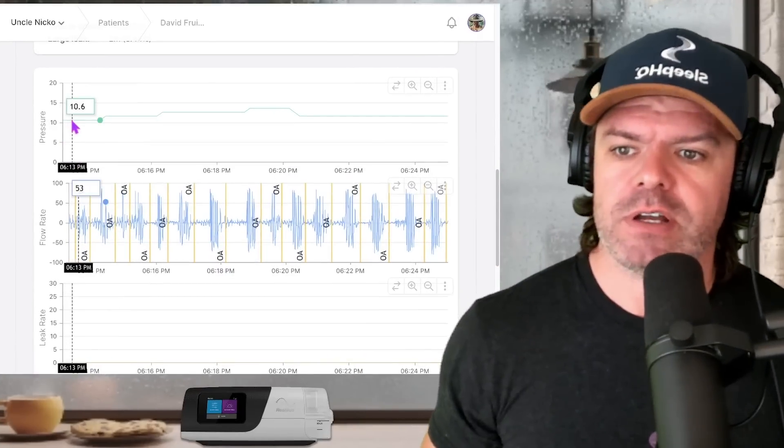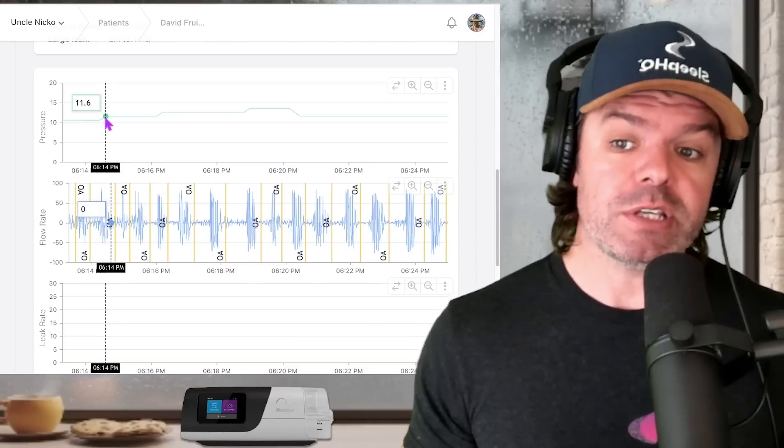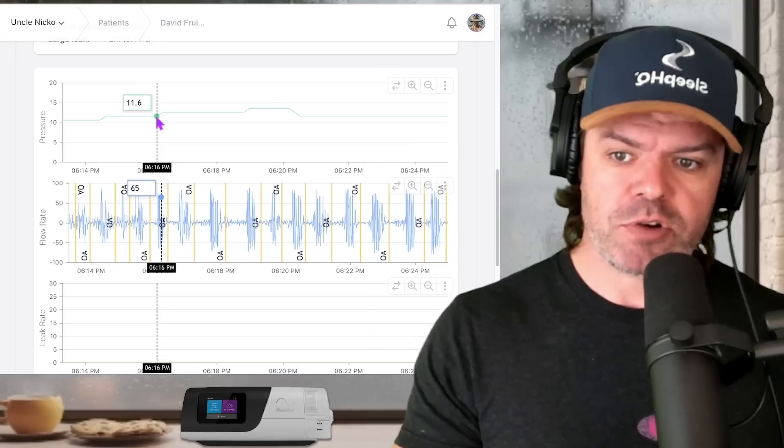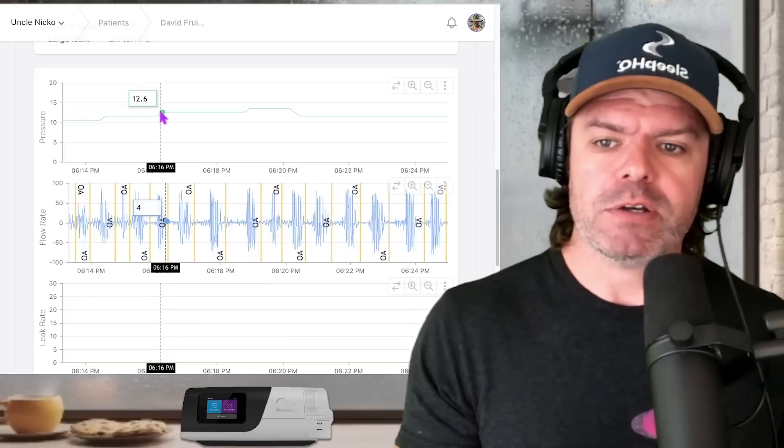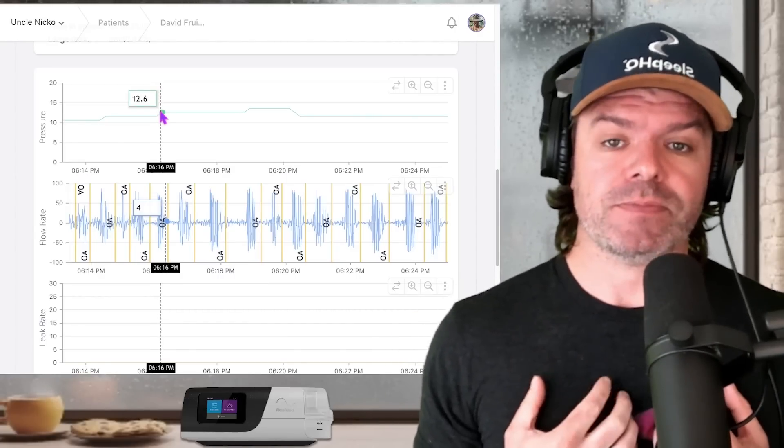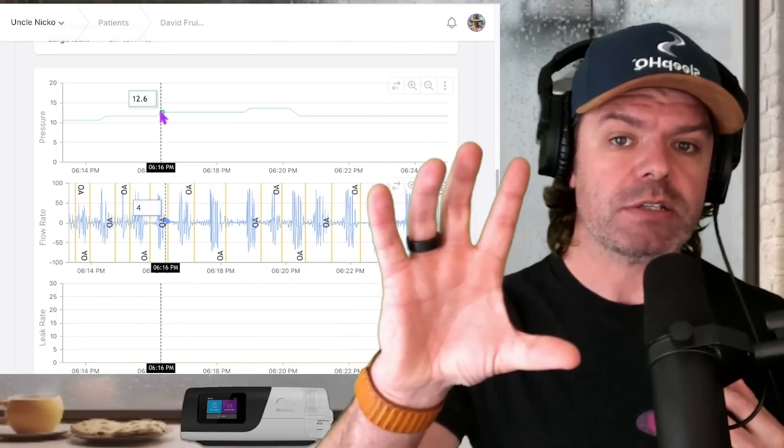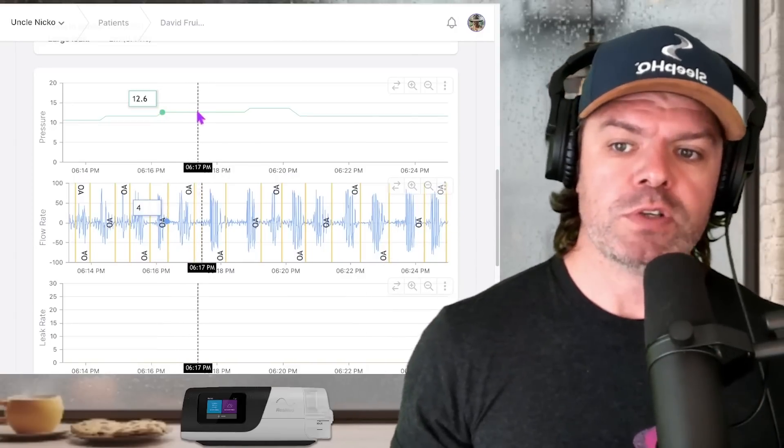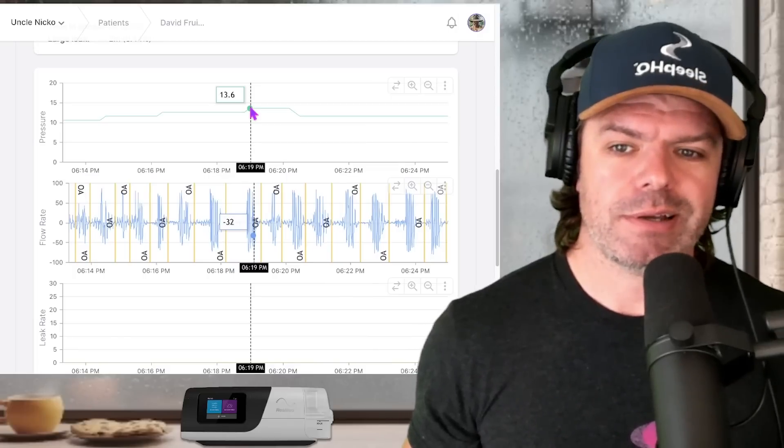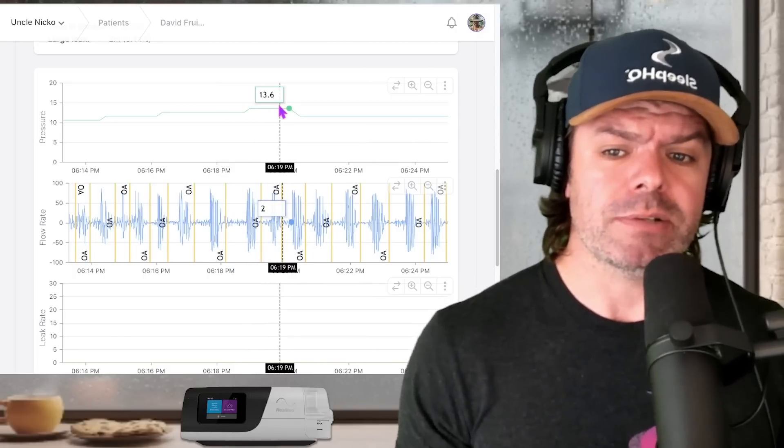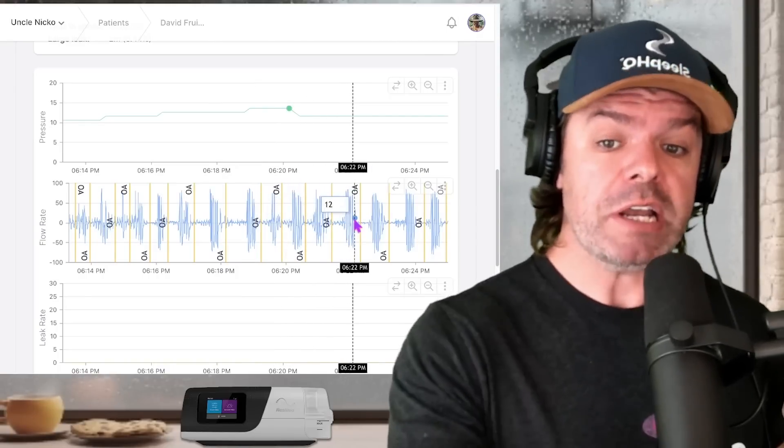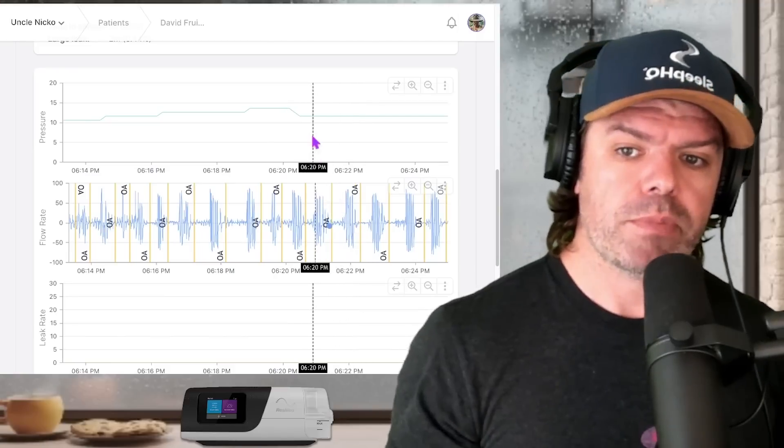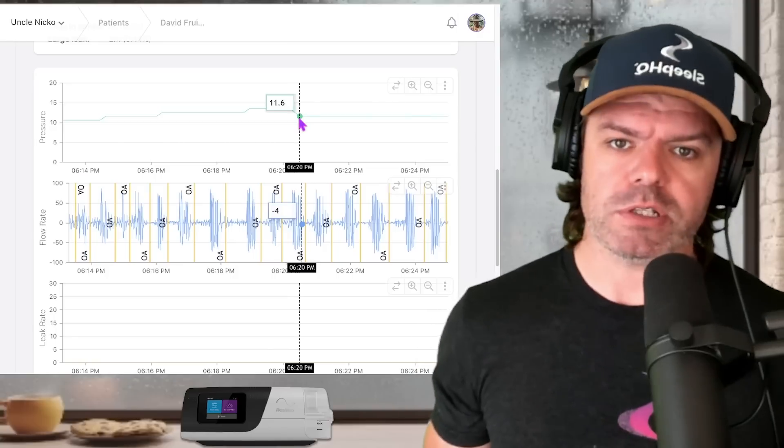Now let's have a look at what the pressure is doing in response to this textbook obstructive apnea. Starts off 10.6 and you can see it gradually moves up to 11.6. It's doing the right thing. He's still obstructive. Goes up again to 12.6. It's trending up which is what you want because the idea is currently there is no air getting into Dave's lungs. So the pressure needs to increase to force air in. That's how it works. All right it pauses for a little bit here and then it goes up again to 13.6. But have a look. This is where it gets really confusing. He's clearly still obstructive the machine knows it. The machine is flagging these events obstructive apneas. But the pressure goes from 13.6 down to 11.6.